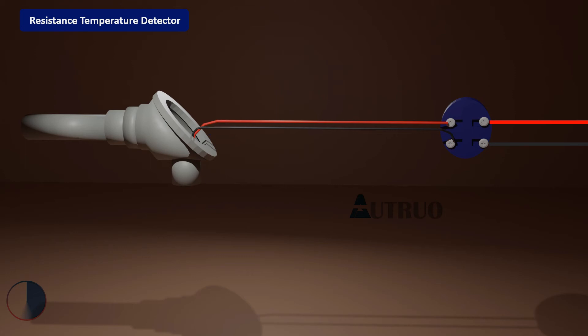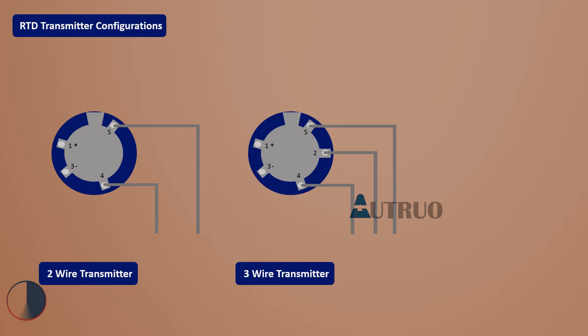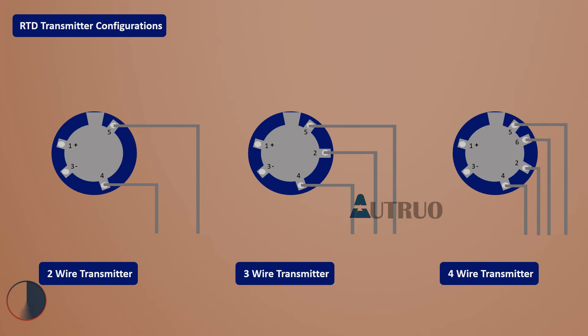Resistance temperature detectors come in three configurations: 2-wire, 3-wire, and 4-wire configurations. 2-wire RTDs can be prone to measurement errors because the connecting wire between the sensing device and terminating point, usually the PLC modules, has its own resistance. This gives room for error. 3-wire and 4-wire RTDs were developed to solve these problems.